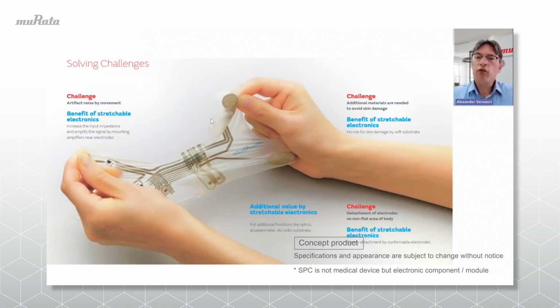So how can stretchable printed circuits benefit medical devices? For patient monitoring devices, traditional materials can cause not only discomfort, but even skin damage for the patient. And in particular, this can be relevant for sensitive skin, such as infants or elderly people. Stretchable printed circuit materials are very soft and so can avoid pressure points and sharp edges, reducing the risk of skin damage and also improving the comfort of use.